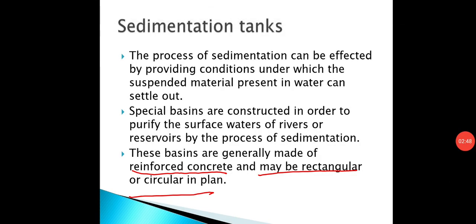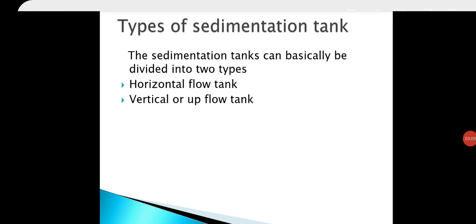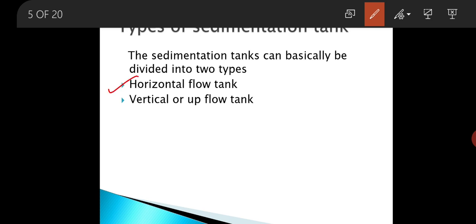A plain sedimentation tank can remove as much as 70% of the suspended impurities present in water. Sedimentation tanks can basically be divided into two types: one is horizontal flow tank, and the second one is vertical or upflow tank.